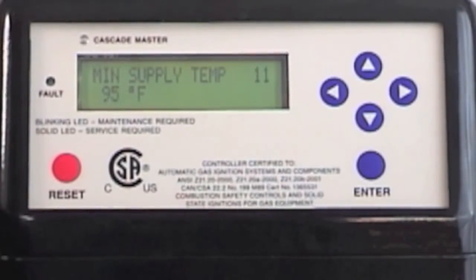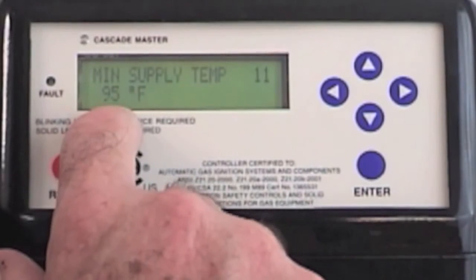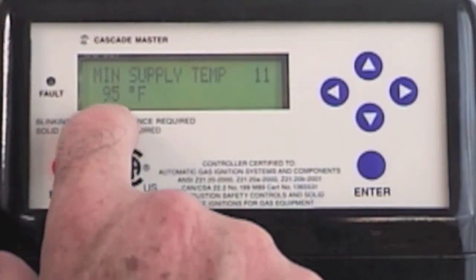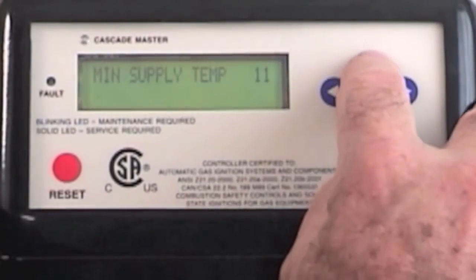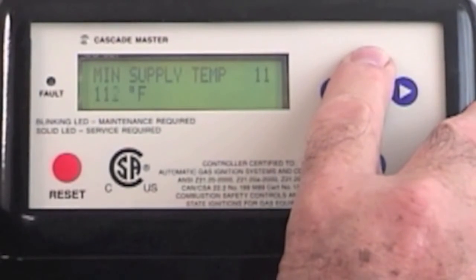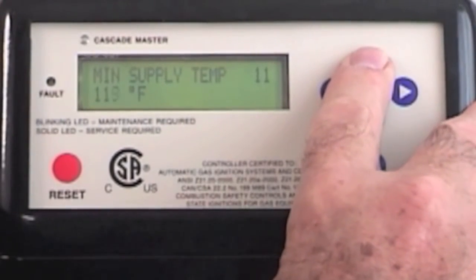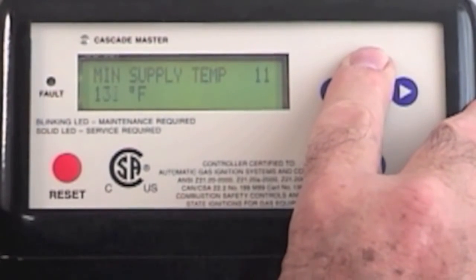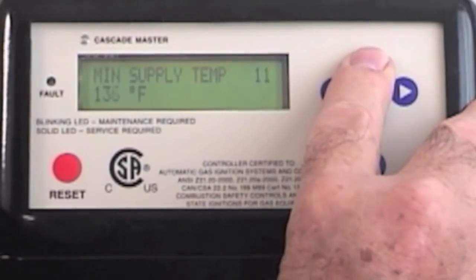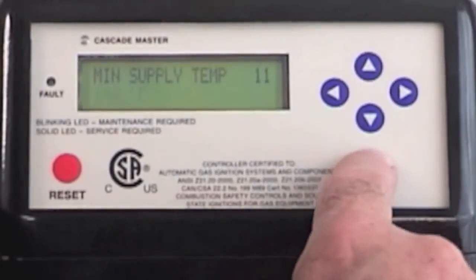In this particular case I have baseboard, and baseboard will not work at anything below 120 degrees normally. So I'm going to recommend changing that to 140. I'm hitting the up button — notice the number is going up. There's my 140. I'm going to hit the enter button.